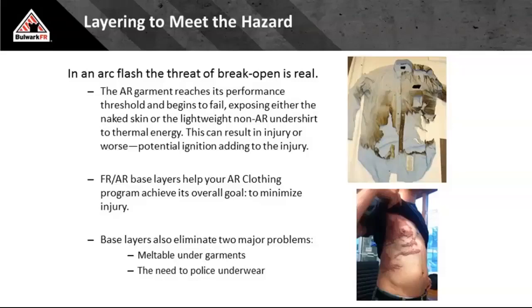Now, the standard says if you're going to wear non-FR underneath, your outermost layer has to not break open. Well, under what conditions? We can have break open because we've exposed it to more energy than either A, the equipment stayed open longer than it needed to, B, I was closer than I thought, or it was bigger than I thought. All of those could potentially break open my outermost layer, exposing that non-FR or, worst case, meltable.